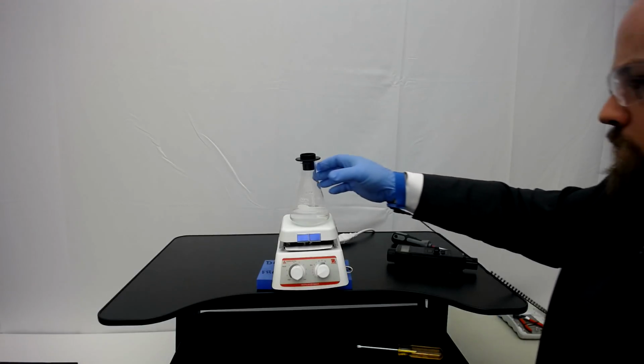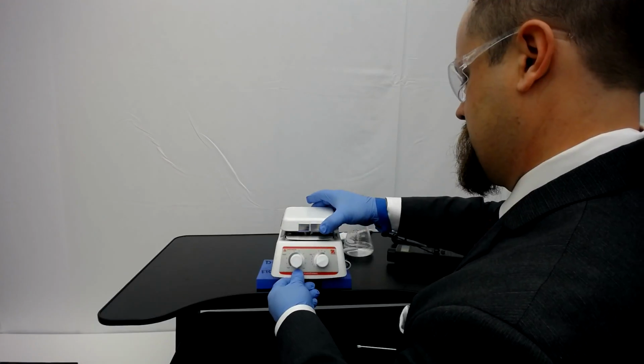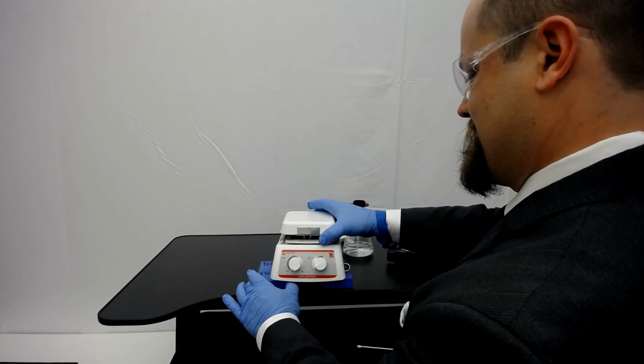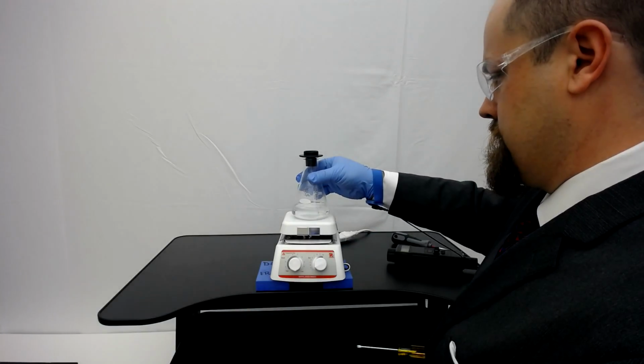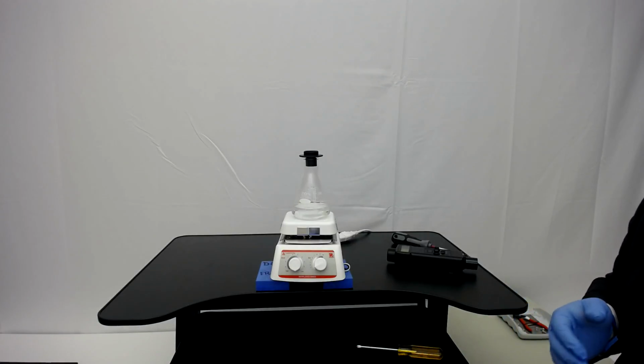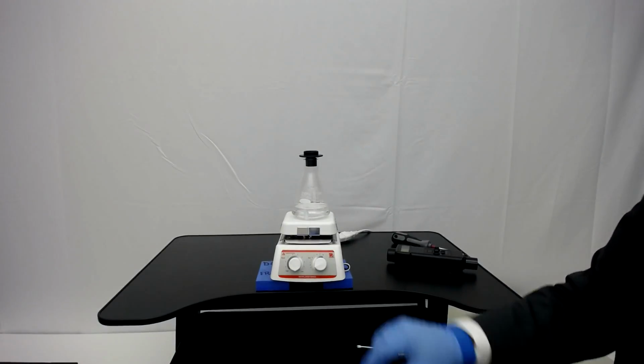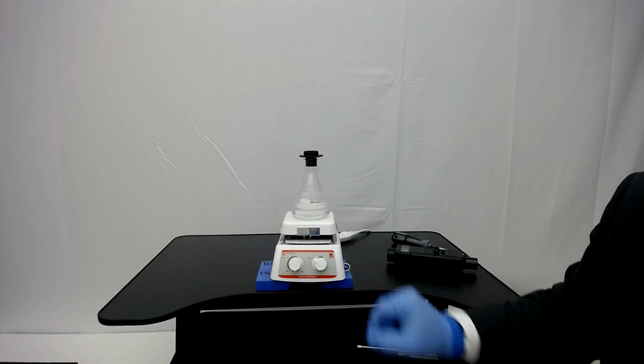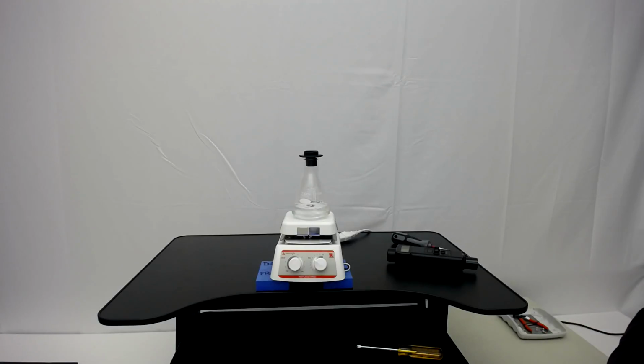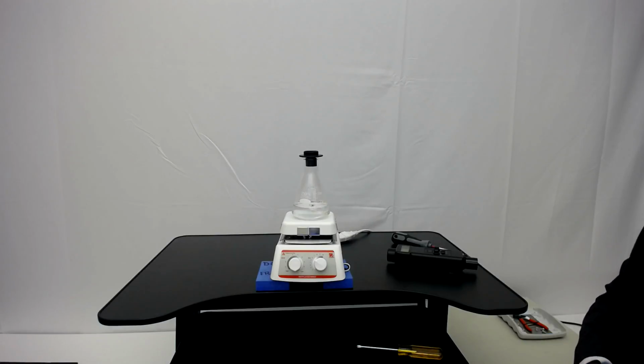All right, so we've done the calibration at 1. I'm just going to adjust this unit so it's on the foam a little better. So it's turning slowly at 1. Next, we're going to turn the speed up to 5 and make sure it increases in speed. If the unit doesn't increase in speed, there's probably something more important than just a calibration going on, and that's when you would contact us, and we would either walk you through a more intensive program or replace the unit. But here it did pick up speed.